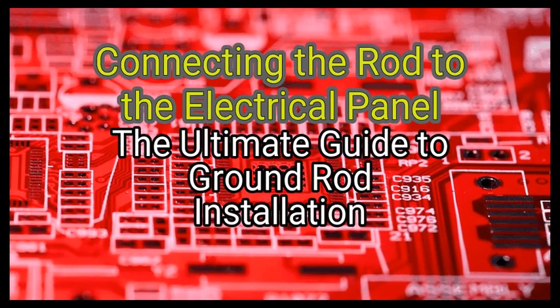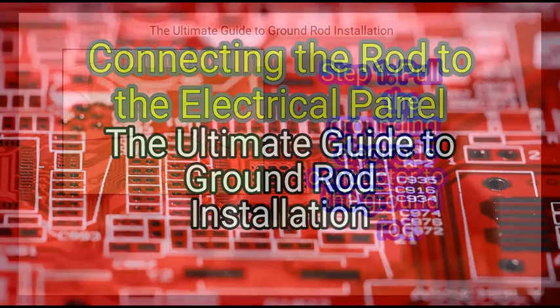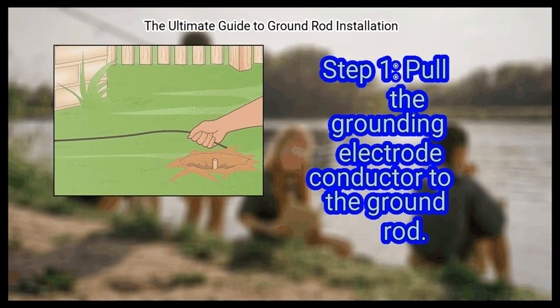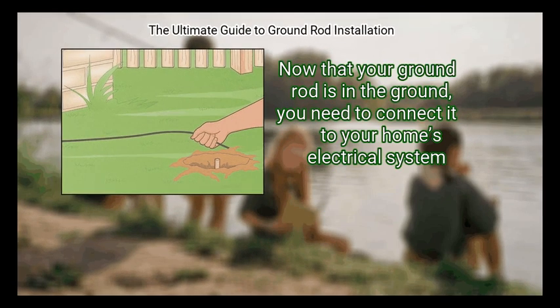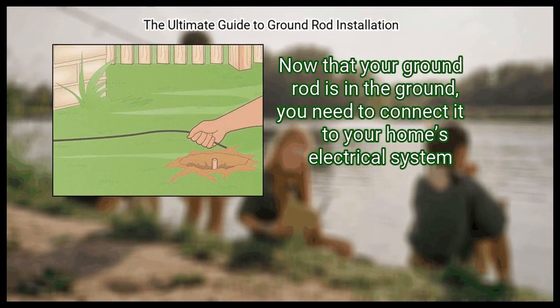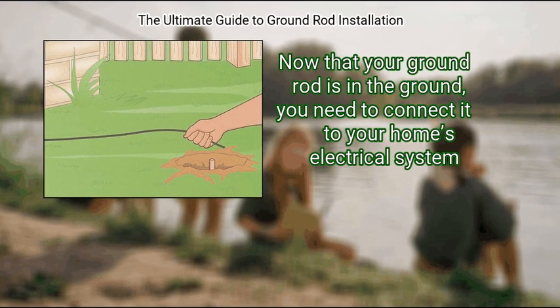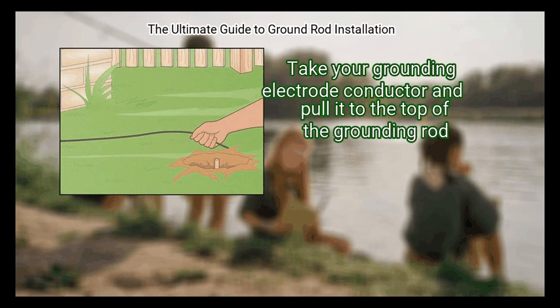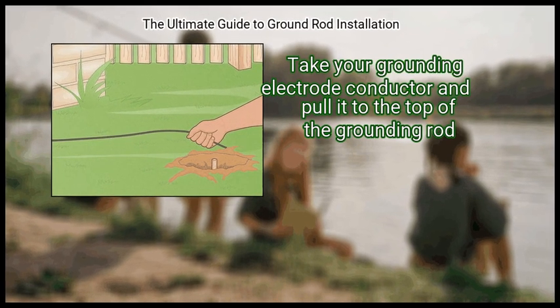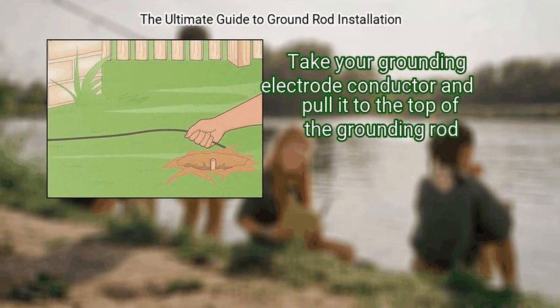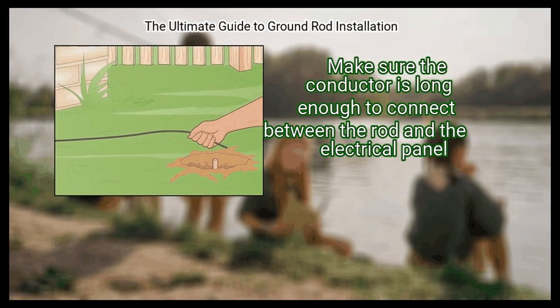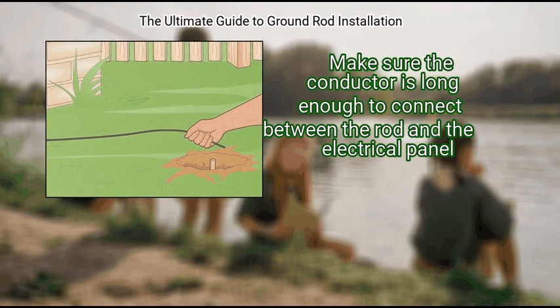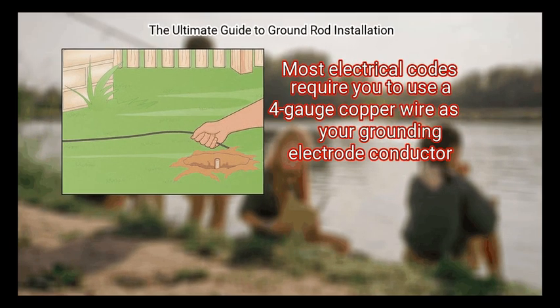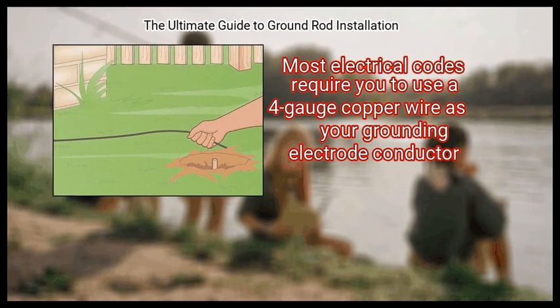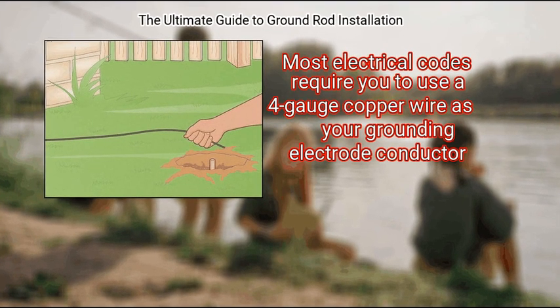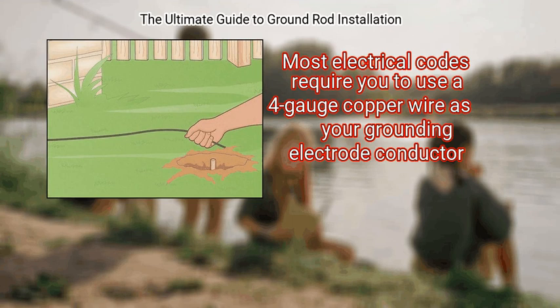Method 3. Connecting the rod to the electrical panel. First, pull the grounding electrode conductor to the ground rod. Now that your ground rod is in the ground, you need to connect it to your home's electrical system. Take your grounding electrode conductor and pull it to the top of the grounding rod. Make sure the conductor is long enough to connect between the rod and the electrical panel. Most electrical codes require you to use a 4-gauge copper wire as your grounding electrode conductor.